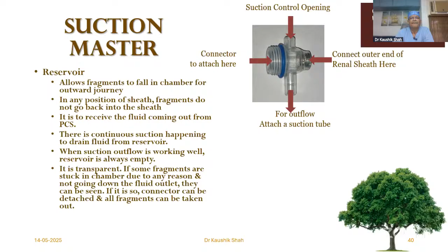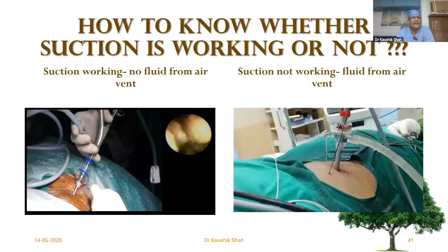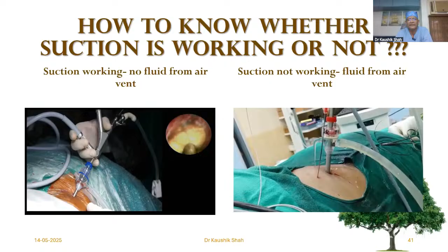It is made transparent so that if you have aspirated a bigger fragment and it's not going downwards, you can see it, and by separating the connector, you can remove those fragments. That's the reason it is separate. Here in the suction chamber, the fluid is completely empty. That means it is working, and when fluid is coming out, that means there is obstruction to the flow of the passage, and that's how you can come to know whether suction is working or not. If the fluid is coming from the air vent, it means suction is blocked. If it is not coming, the chamber is empty. That means our system is working perfectly.